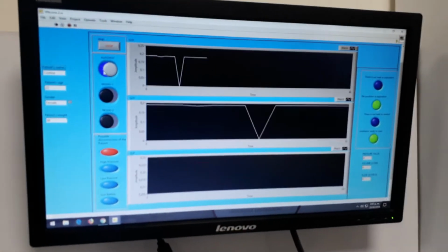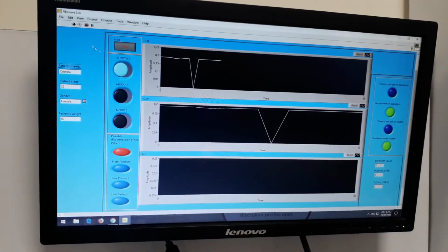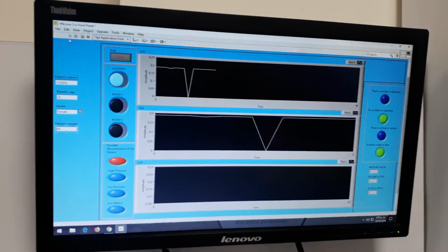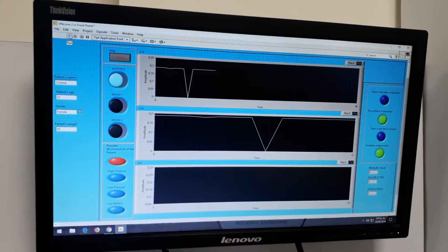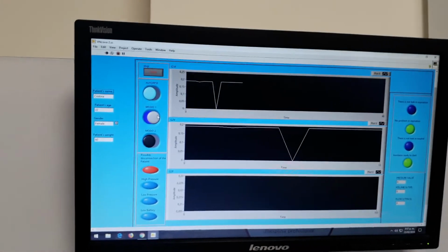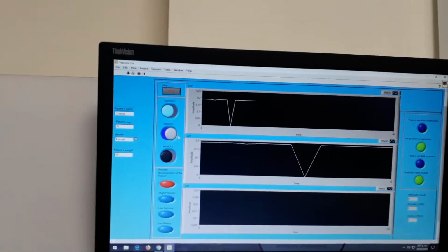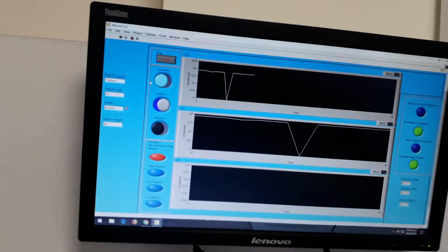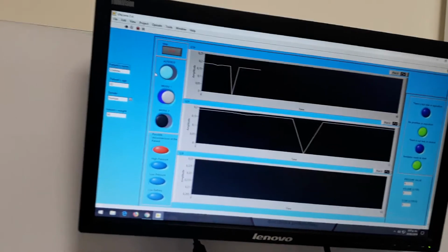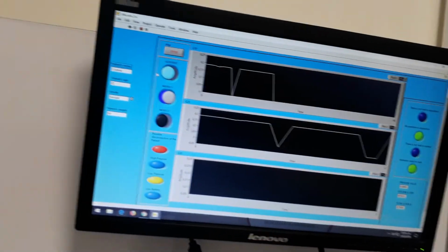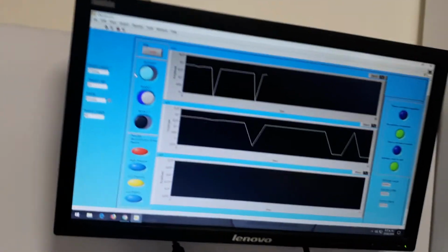So, the second part is mode 1. Mode 1 is ventilation with pressure support. It is a spontaneous ventilation mode in which each inspiratory effort of the patient is assisted by the ventilator up to a programmed limit of inspiratory pressure.